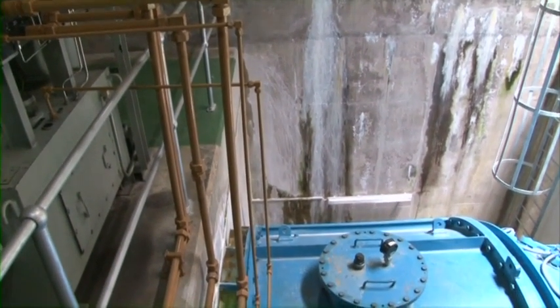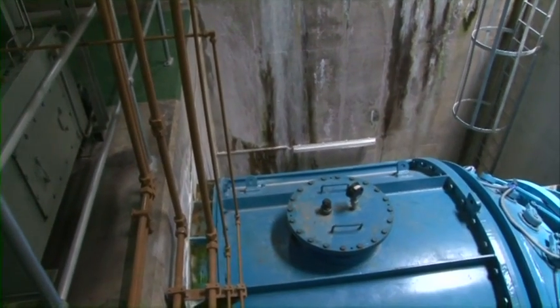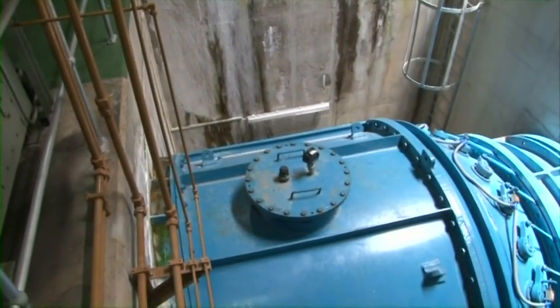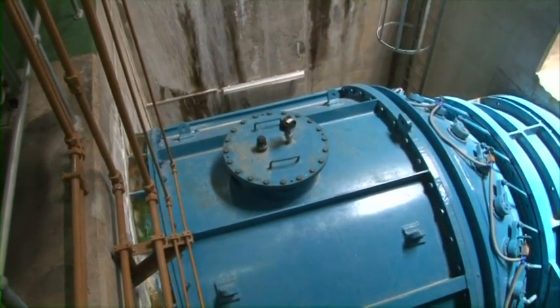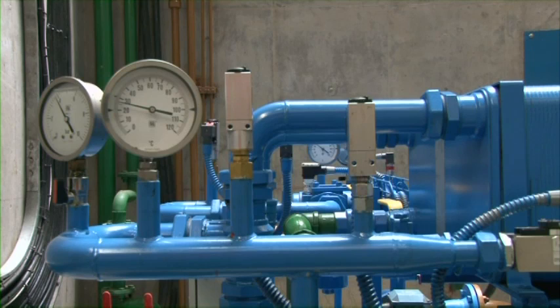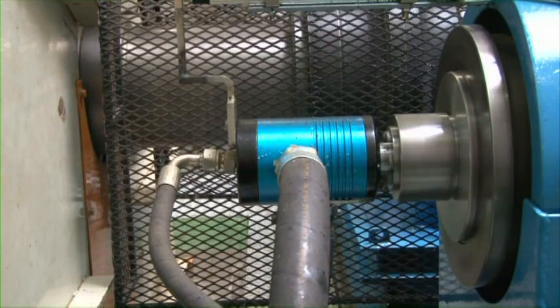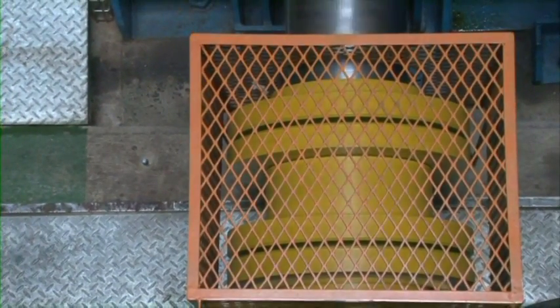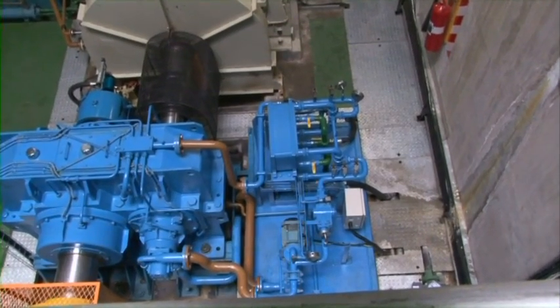The second auxiliary item that we have is the gearbox oil lubrication system, which is a simple oil system which lubricates the gearbox and controls the pressure and the temperature at which the gearbox operates. The third auxiliary system of note is the generator lubrication oil system, which is also a very simple oil system which lubricates the two bearings on the drive end and the non-drive end of the generator. To generate power, we need to synchronize with the Eskom grid, and for that we need three things. We need a frequency of 50 Hz, a speed of 750 RPM, and a voltage on our generator bus bar of 6.6 kV.